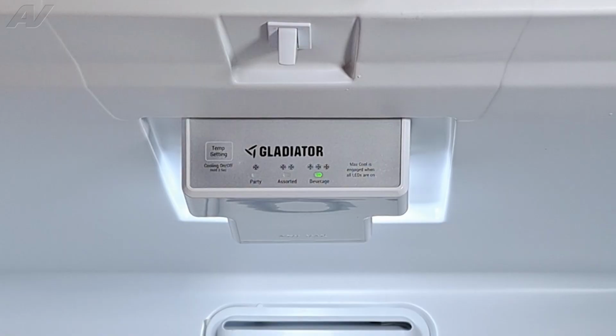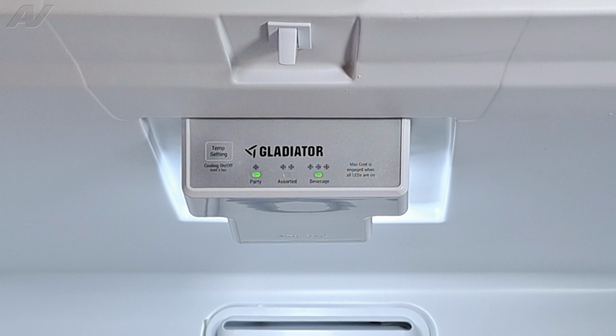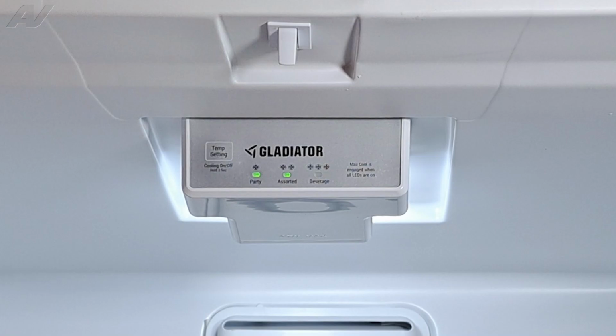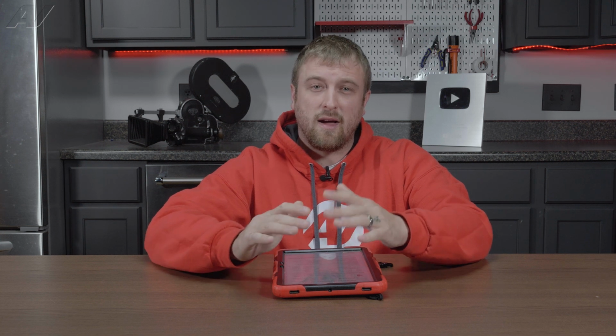It says FC thermistor. This is the actual temperature probe inside the freezer. And then you have the third LED, which is the very last one. This LED, if it's blinking, indicates that you have a problem with the evaporator thermistor. Now, there are ways for this unit to store multiple error codes, so you may run into a situation where you have the first LED and the third LED blinking. That would mean that you have an evaporator thermistor problem and a control problem. Or you may find where maybe the first LED and the number 4 LED are blinking. This would indicate that you have a problem with the control and you have a problem with the freezer compartment thermistor. Make sure you go to your tech manual to find out which LED blinking corresponds to your unit.